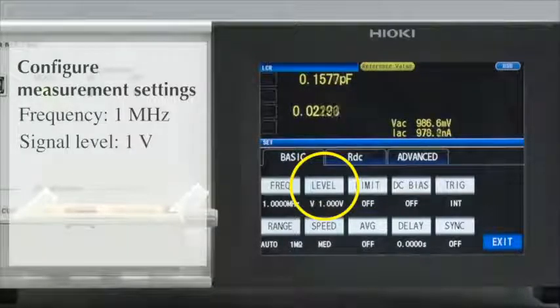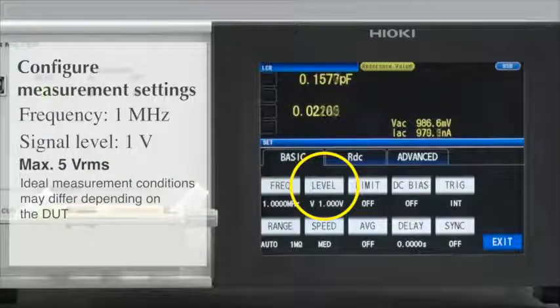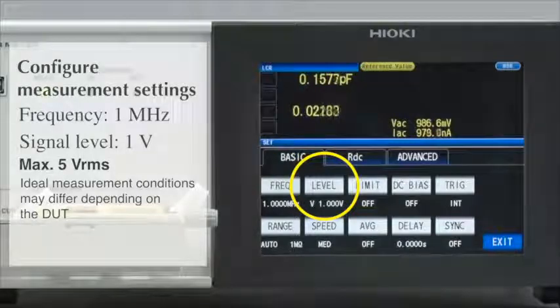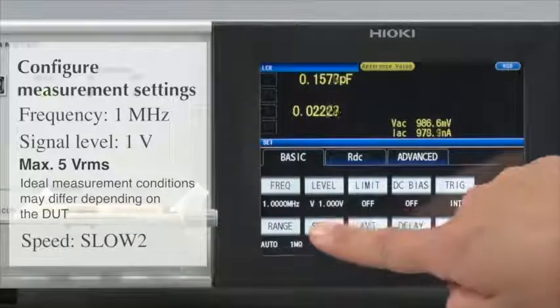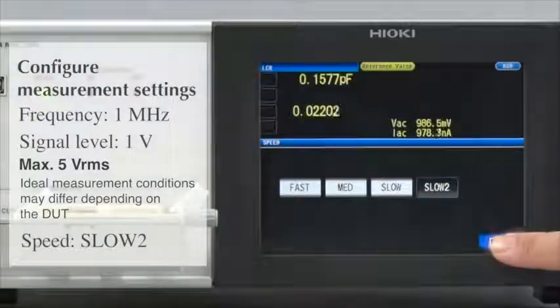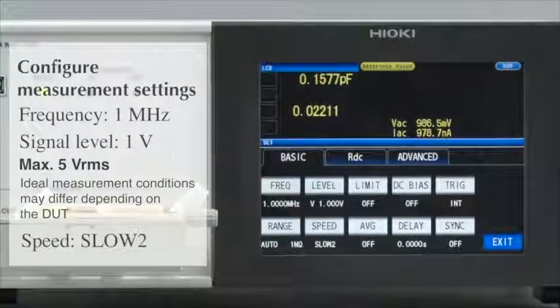The measurement voltage will remain at the default setting of 1 V. Set the speed to Slow 2. By selecting Slow 2 as the measurement speed, you can achieve more stable measurements.